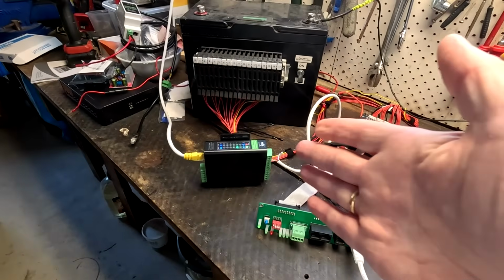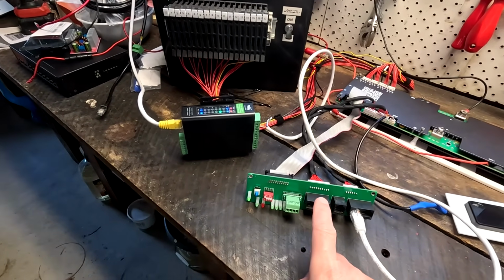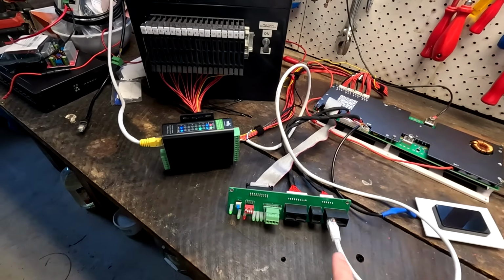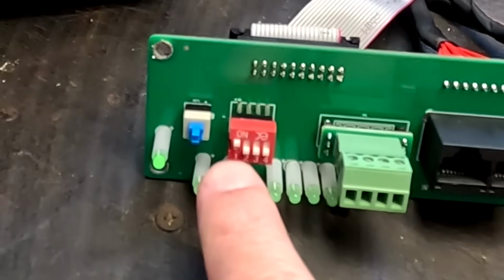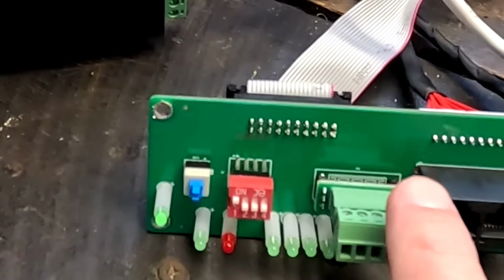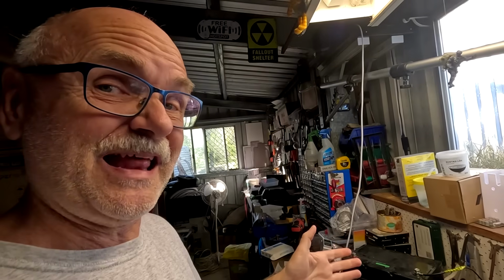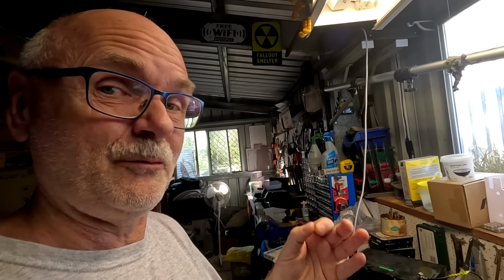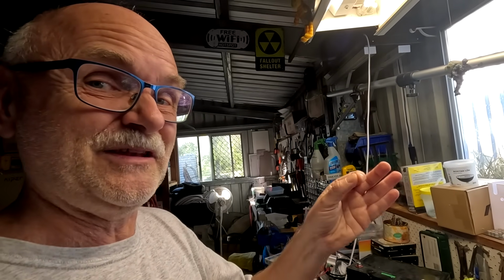Because we haven't set the dip switches correctly. This setup obviously only works if you have a master BMS. This one sits on dip switch 1000, so this is the first slave actually. The slave BMSs don't send any data via RS485 to other BMSs or to the host computer. You always need to have a master which is actually triggering the slaves to give them their data.